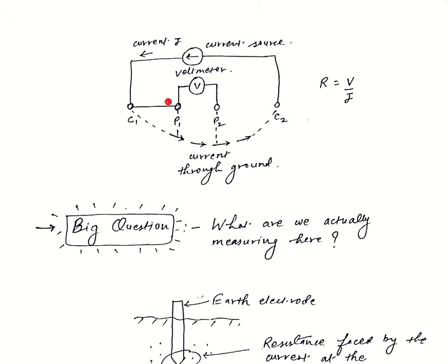C1 and P1 are shorted here as I have told you already. The voltmeter will measure the potential drop between the terminals P1 and P2. The instrument tells us the result, that is earth resistance, by calculating potential drop divided by current flowing as per Ohm's law.